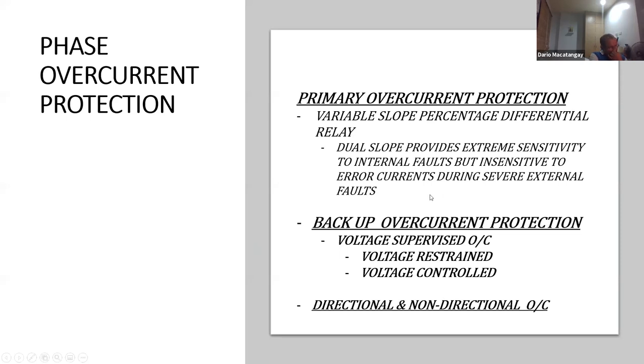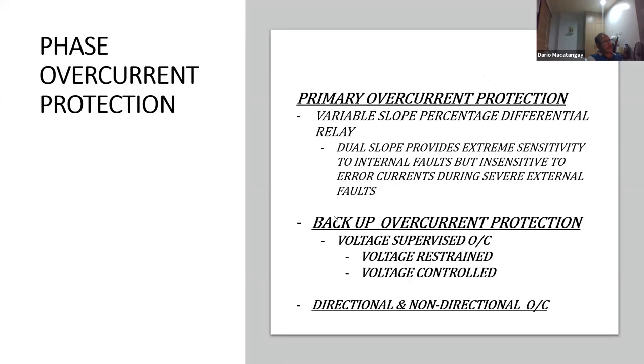So, differential operation: you have two CTs. They are monitoring the input and the output to the differential relay. So if the fault is external to that monitoring zone, then you have an external fault. If the fault is within that zone, then you have an internal fault. So for example, if it is a generator protection, the generator winding itself is inside that protection zone. So when you have a fault in the generator, then you have an internal fault. You have to provide that extreme sensitivity. That's called your differential sensitivity.